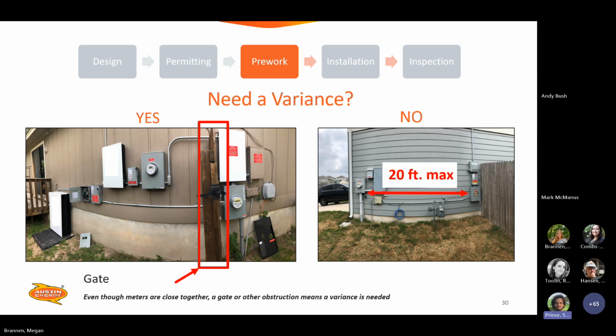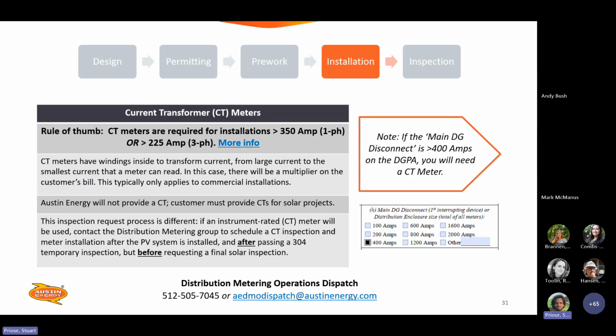Moving along. Okay, so CT meters. When do you need one? CT meters are for larger services. So if you've got a project that has a disconnect that's 400 amps to 600 amps, or 400 amps or larger, you'll need an instrument rated meter.